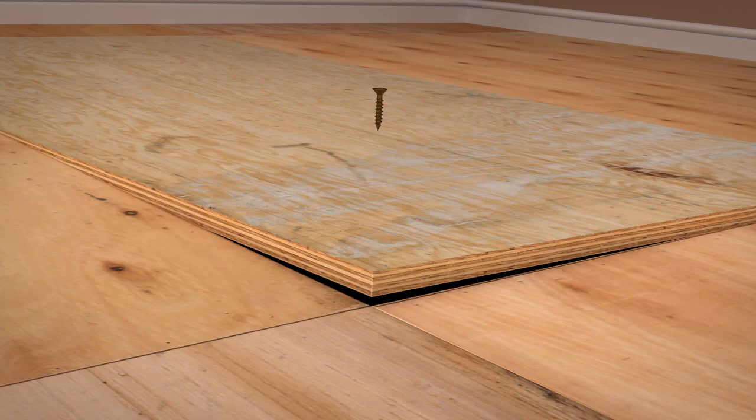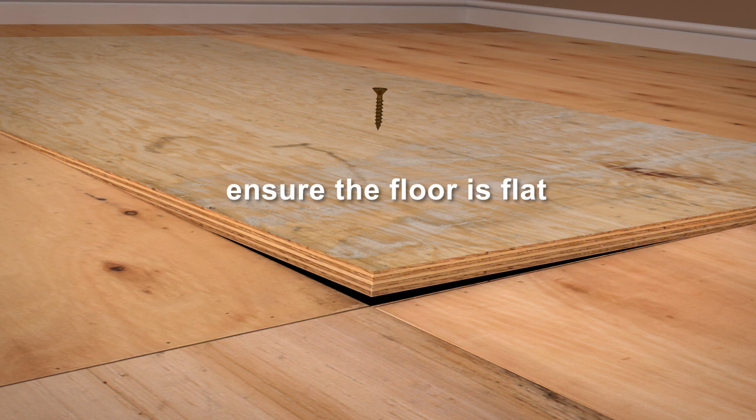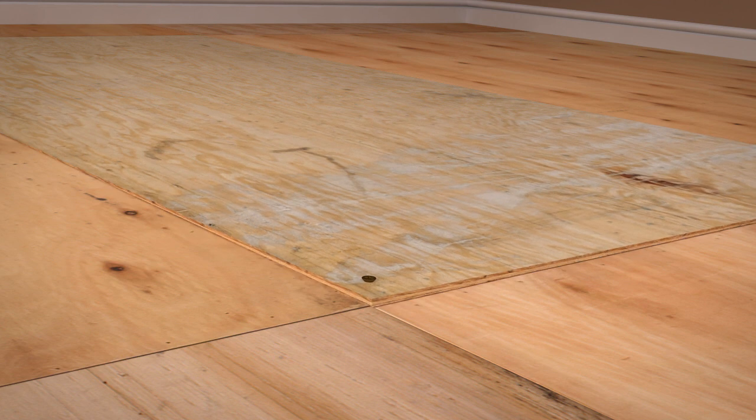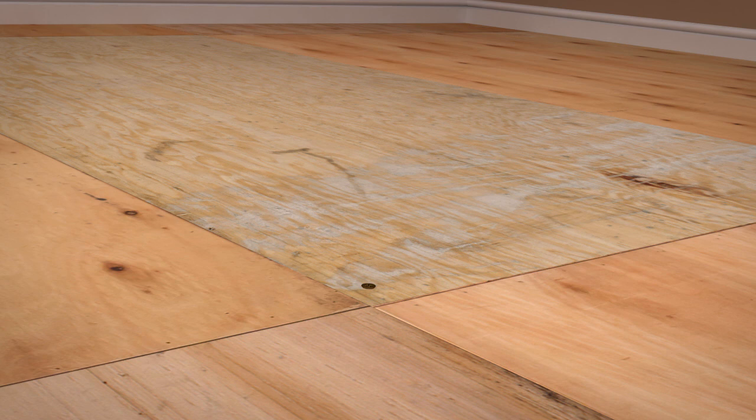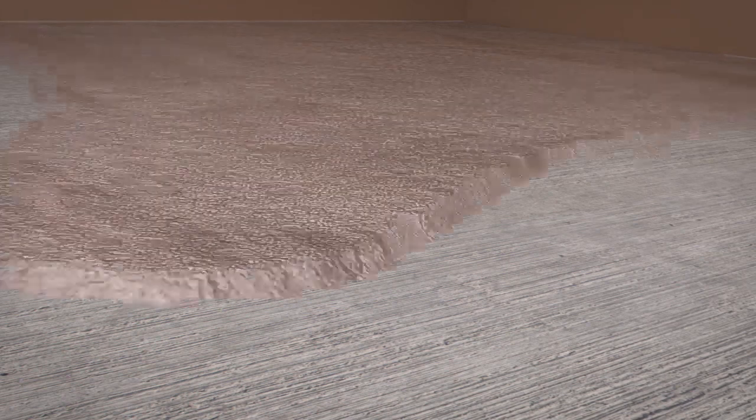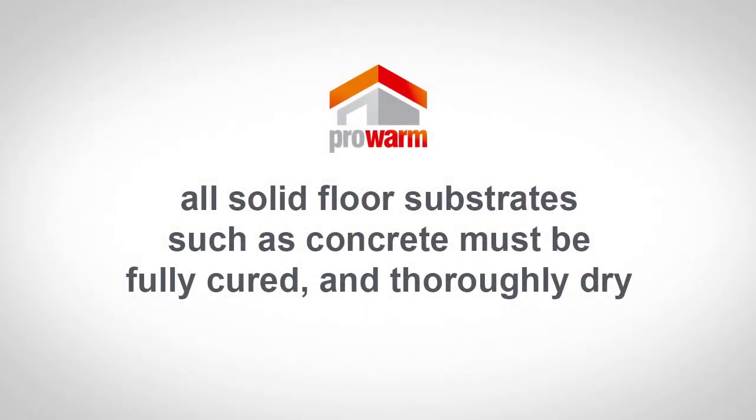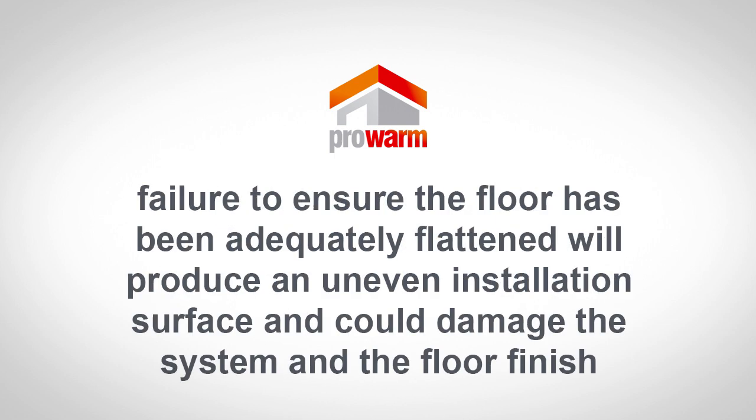Before you install the ProWarm Advanced Overfloor Heating Panel, you must ensure the floor is flat. If installing on a wooden subfloor, ensure all plywood boards are flat, with no protruding nails, screws, and are completely free from debris and solidly fixed down. If installing onto a concrete base, use a suitable leveling compound to flatten out any bumps in the surface. All solid floor substrates, such as concrete, must be fully cured and thoroughly dry. Failure to ensure the floor has been adequately flattened will produce an uneven installation surface and could damage the system and the floor finish.